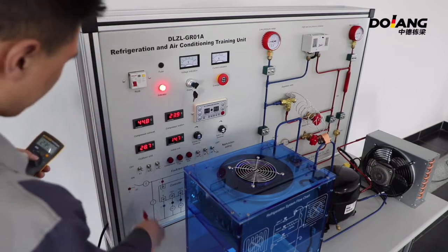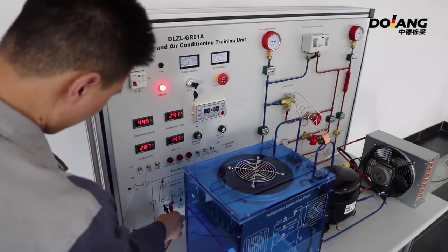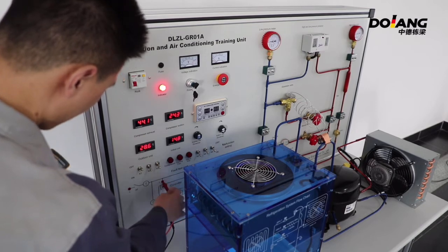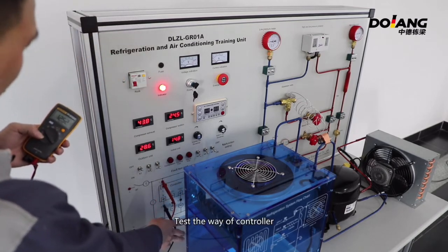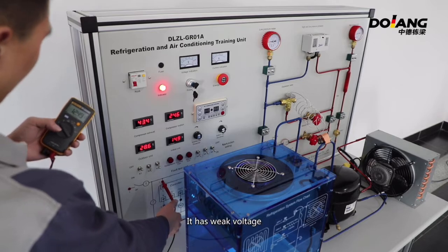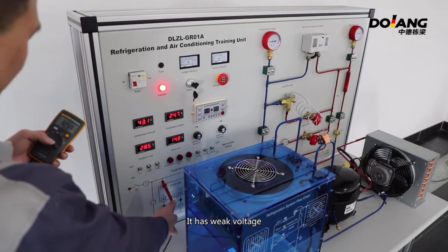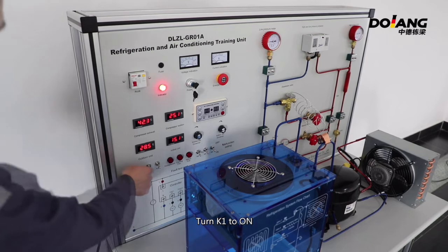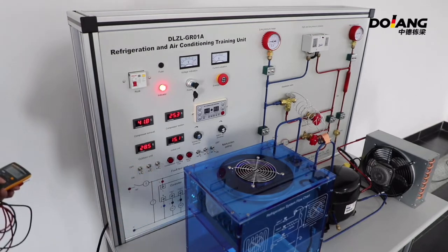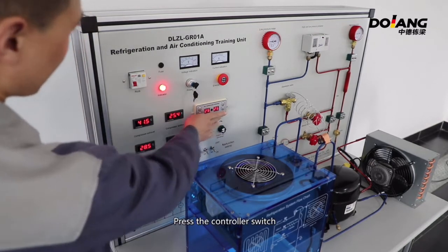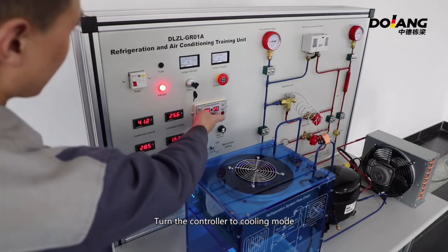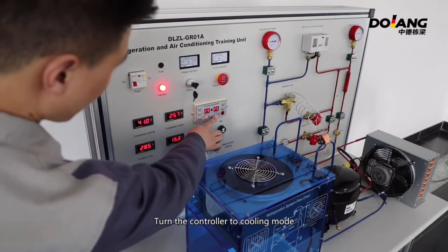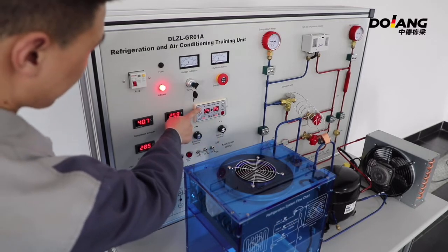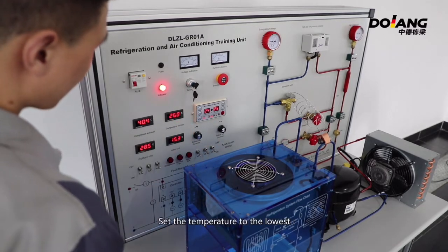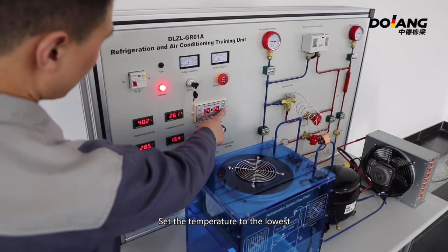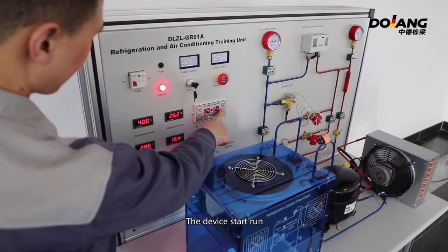There is voltage here. Test the voltage of the controller. It has a weak voltage. Turn K1 to on. Press the controller switch. Turn the controller to cooling mode. Set the temperature to the lowest. The device starts to run.